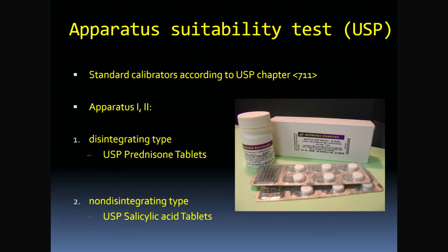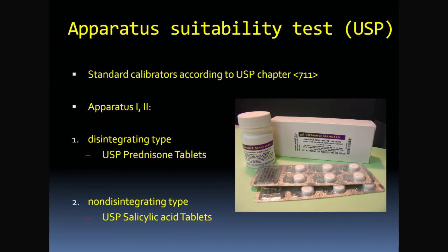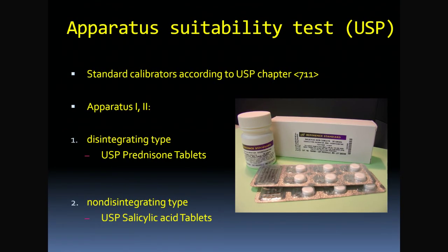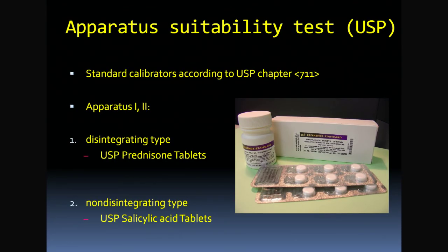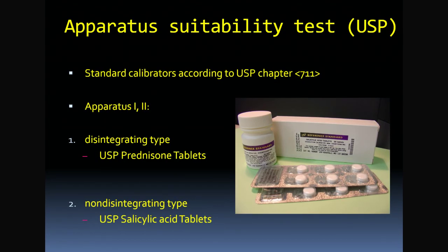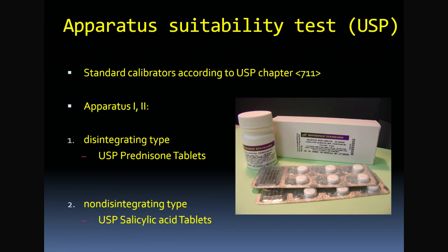If your measured dissolution rate for these standards falls outside the tight statistical range provided by the USP, how would that mechanical discrepancy undermine the kinetic profile of an unknown drug formulation? By verifying the hardware using these two distinct physical mechanisms, disintegration and erosion, we mathematically confirm that the mass transfer coefficient in our vessel is standard and reproducible.